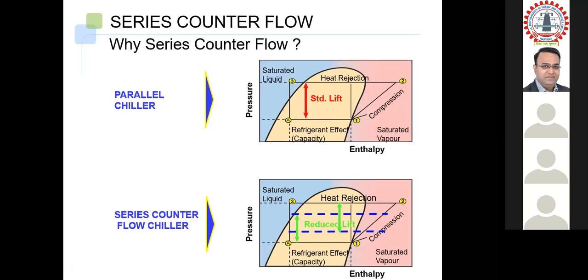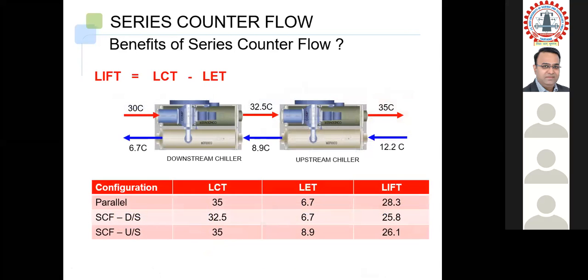The lift is normal in the case of a standard chiller arranged in a parallel configuration. When you put the same chillers in a series counterflow arrangement, in one chiller the chilled water temperature goes up, and in the second chiller the condenser water temperature goes down. So the lift on each chiller reduces, like the green portion you can see. One chiller has this lift and the second chiller has this lift. Both chillers have less lift, and their power consumption reduces significantly. This is the benefit.